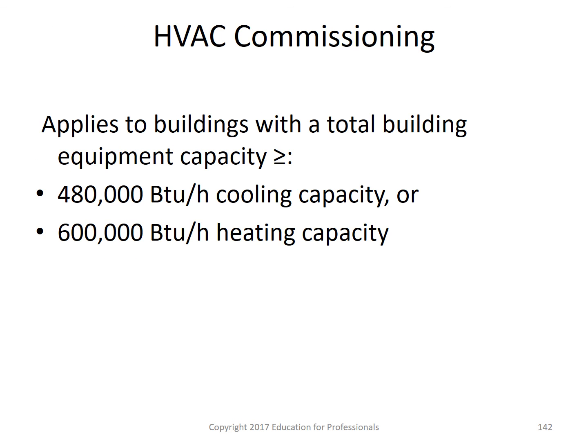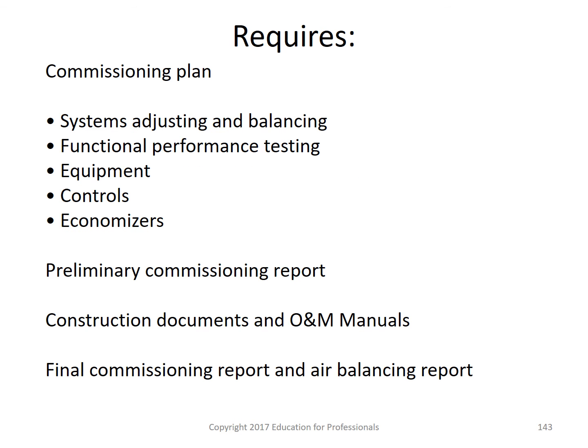And the all-important HVAC commissioning applies to buildings with a total building equipment capacity greater than or equal to 480,000 BTU in cooling capacity or 600,000 BTU in heating capacity. So what needs to be done under the commissioning plan? That's systems adjusting and balancing, functional performance testing, equipment testing, controls testing, and economizers testing, which generates a preliminary commissioning report. Also, you have to tender construction documents and O&M manuals, and a final commissioning report and air balancing report.